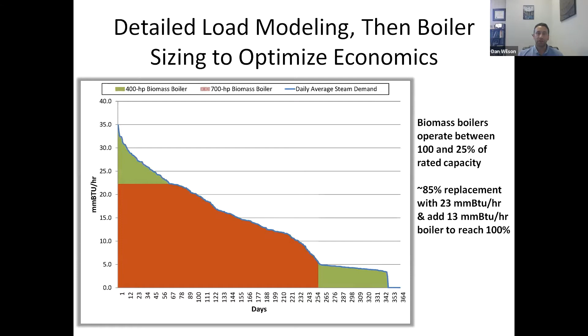We do a fair amount of coming in after the fact to help troubleshoot systems, and I would say the number one, possibly number 2 issue that we run into with the wood energy systems, if there is a problem, is associated with the size of the unit. They turn down to about 25 to 30% of their rated capacity, a little lower at times, but typically you don't want to run them much below that. And so we find that systems that are much bigger than the loads that they're serving can have operational issues. And so a lot of times we'll go in and do a load model after the fact to compare that to what the installed capacity or design capacity for the system was, and identify items there.